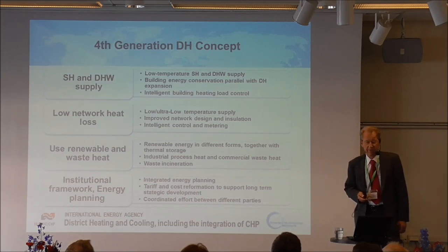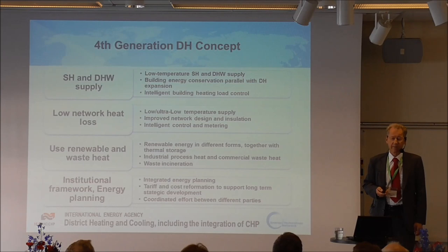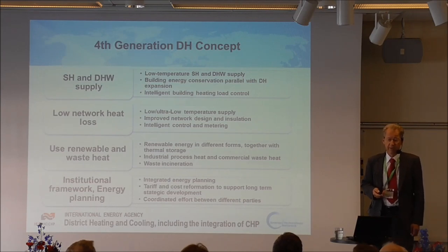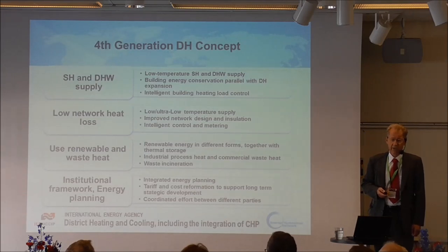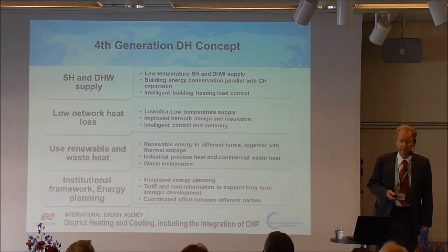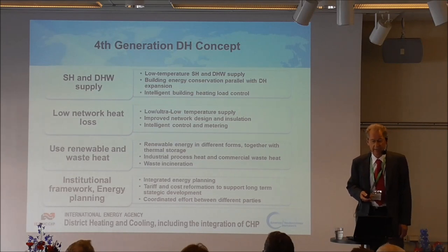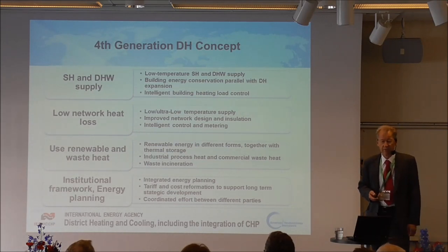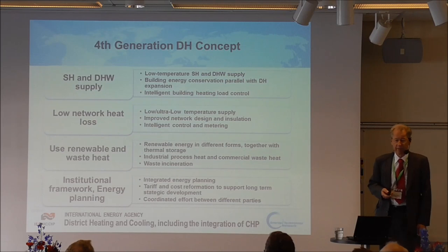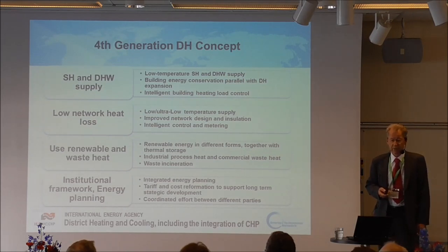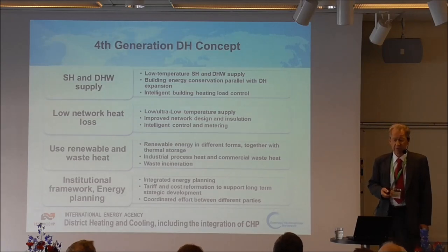We want buildings to be heated for space heating and supplied with domestic hot water based on low temperature. So we have to do something in the buildings. New buildings can easily be prepared to make use of low temperatures. We can control existing buildings better, so low temperature is possible, and we can cool down the return temperature much more.